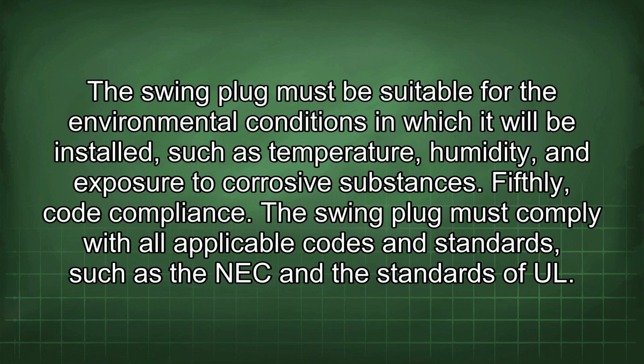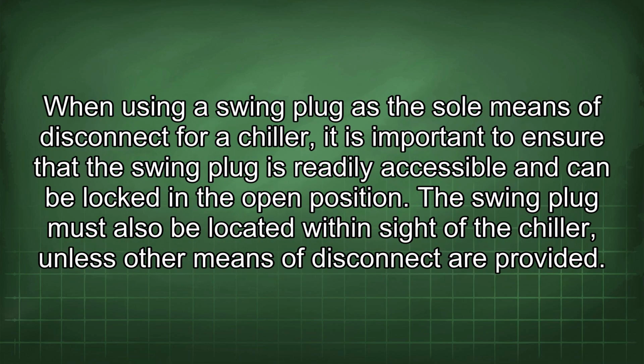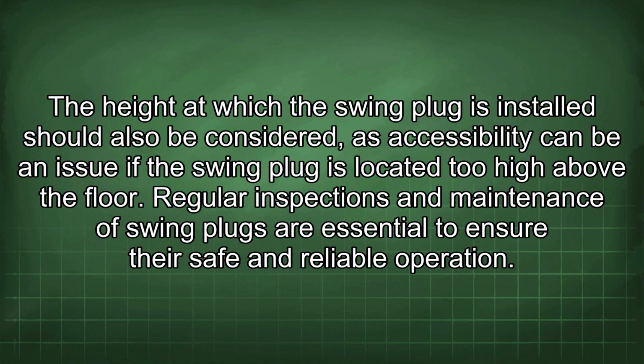Fifthly, code compliance. The swing plug must comply with all applicable codes and standards, such as the NEC and the standards of UL. When using a swing plug as the sole means of disconnect for a chiller, it is important to ensure that the swing plug is readily accessible and can be locked in the open position. The swing plug must also be located within sight of the chiller unless other means of disconnect are provided. The height at which the swing plug is installed should also be considered, as accessibility can be an issue if the swing plug is located too high above the floor.